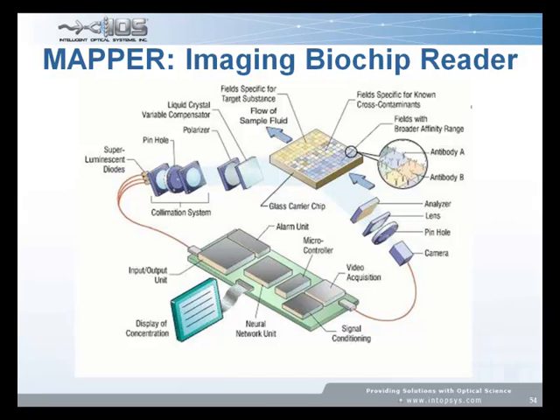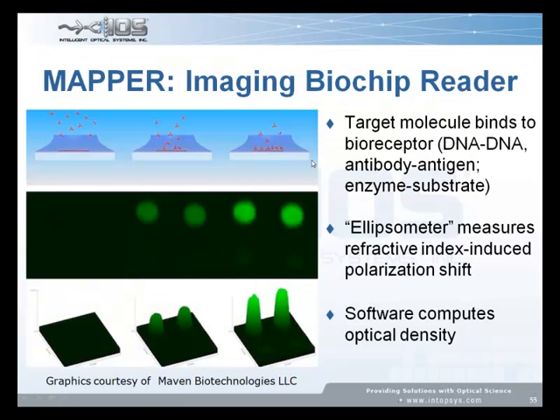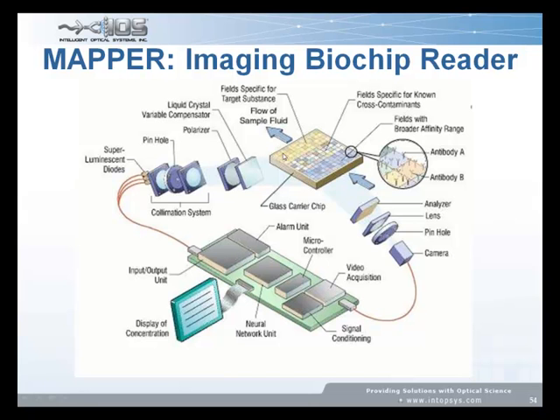The way this works is really quite simple. What we're doing is measuring the plane of polarization of light that's reflected off of the surface of a biochip. So it works on total internal reflection. We're shining polarized light in from the bottom, looking at polarized light coming out. And what we're actually able to do is, in real time, look at binding events. Anything that binds on the surface of this chip changes the local optical density. So actually, there's a layer of stuff that becomes thicker and also has a different refractive index than what you start with.